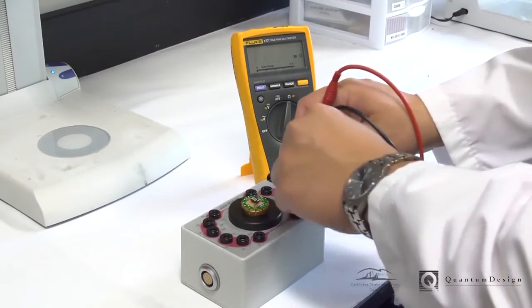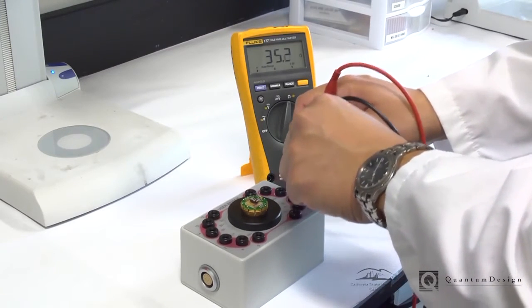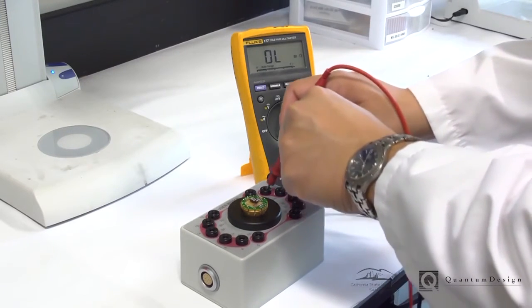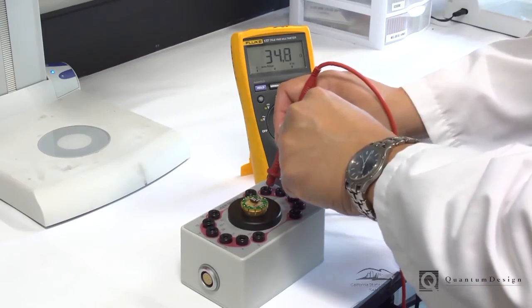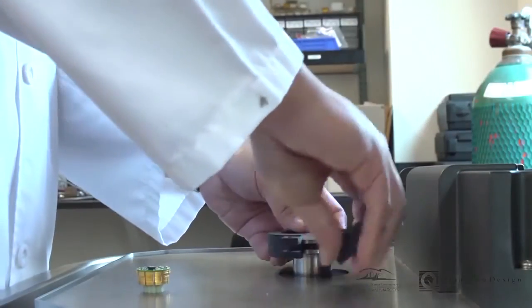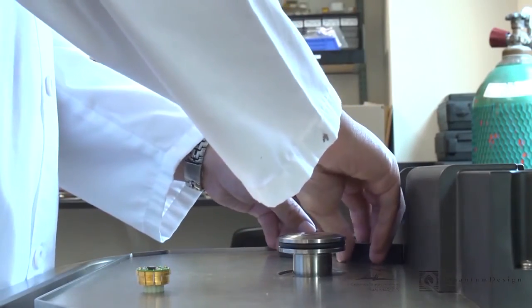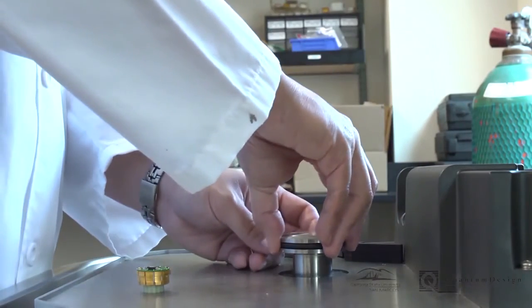You can use the puck box and a standard multimeter to check to see whether you have made good ohmic contacts. Once you are satisfied with your puck contacts, it's time to load the sample into the instrument.